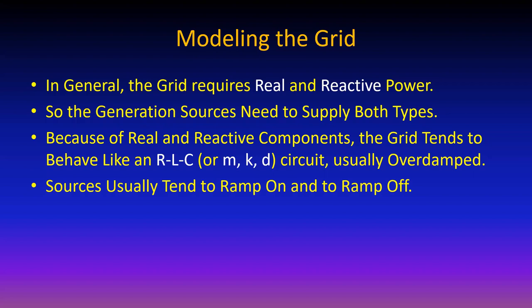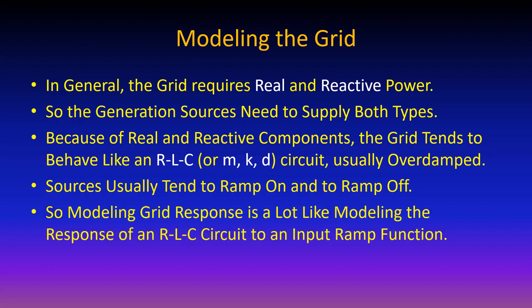One thing is sources tend to either ramp on or ramp off. So if you model this, the grid response is a lot like modeling the response of an RLC circuit to an input ramp function, or like a set of shock absorbers on an automobile hitting a big bump in the road. How are they going to respond? That's really important to know, because then you can add additional components and structure to eliminate any negative result of that kind of response.